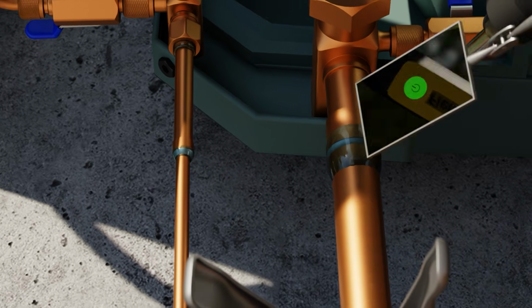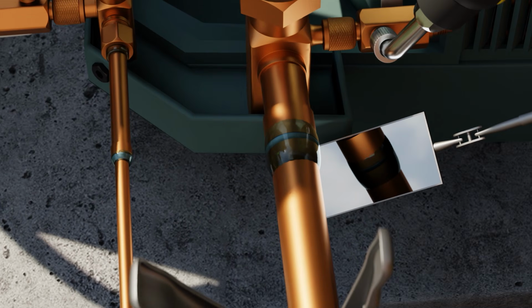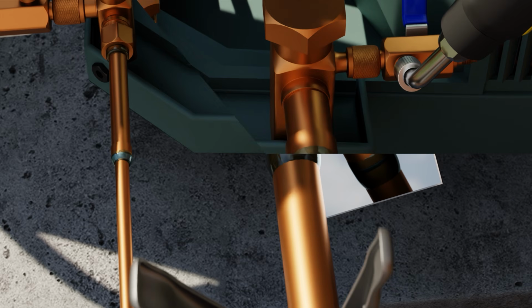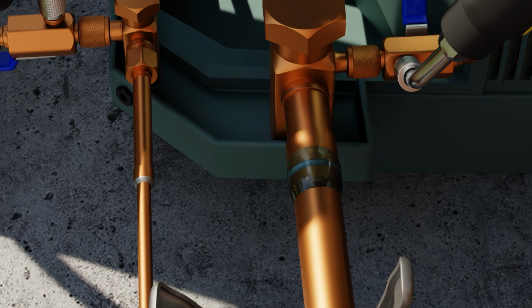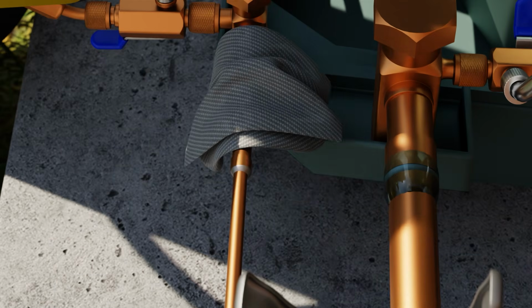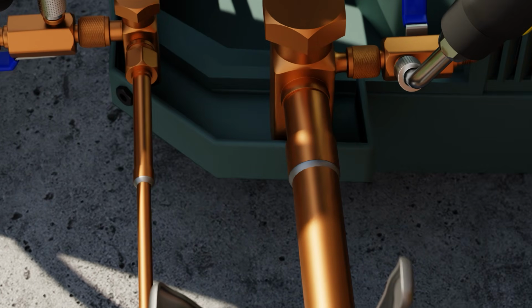You're now going to leak test each connection with the spray-on leak reactant, checking for bubbles visually. Don't skip this step. Look for even tiny microfoam in the bubble solution. Here we show what a good size leak would look like with Refrigeration Technology's Big Blue leak reactant. Next, clean the solution off of all the connections.